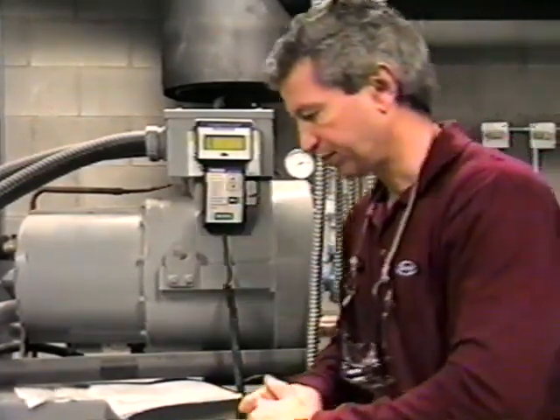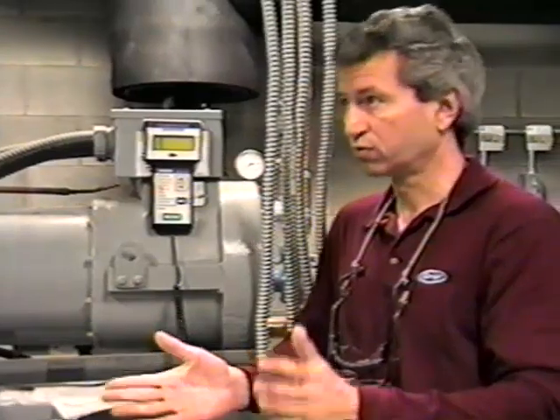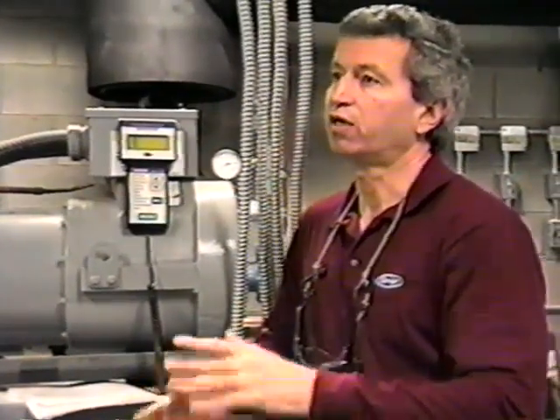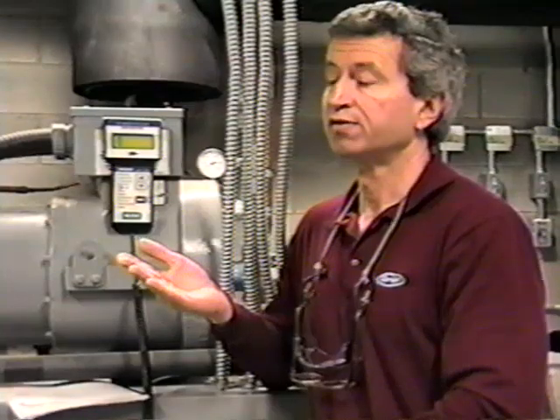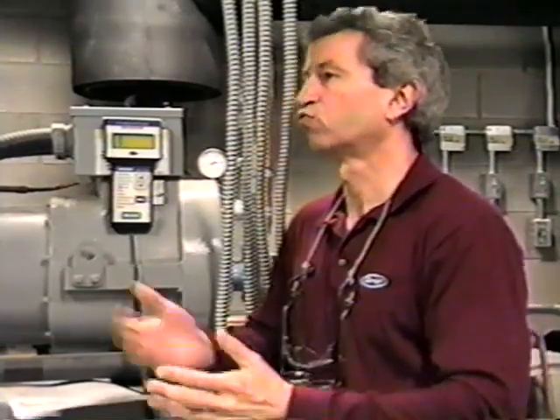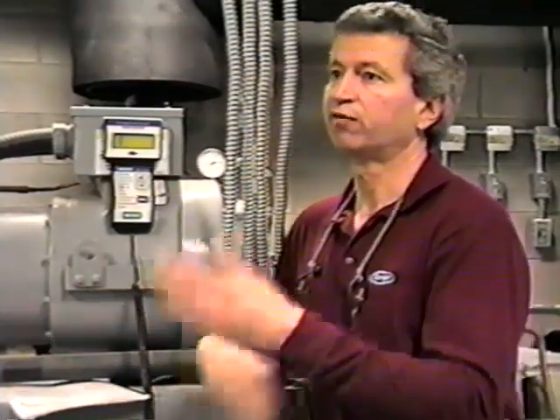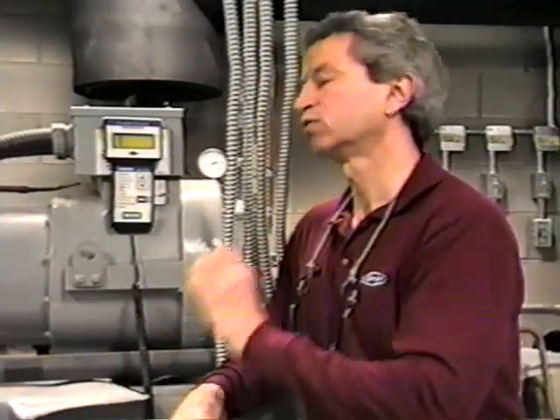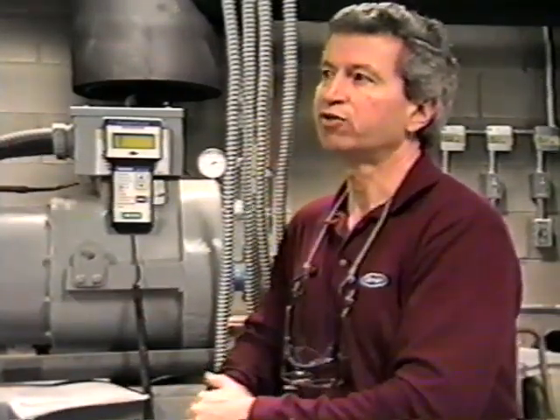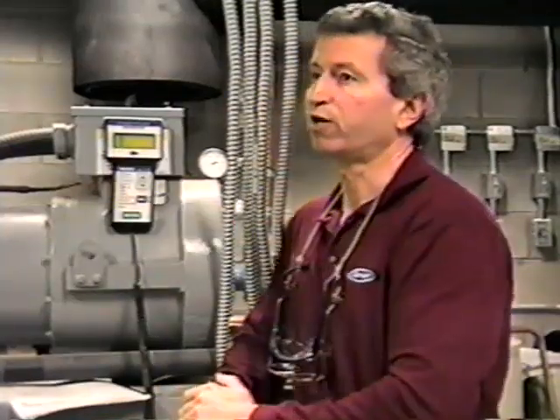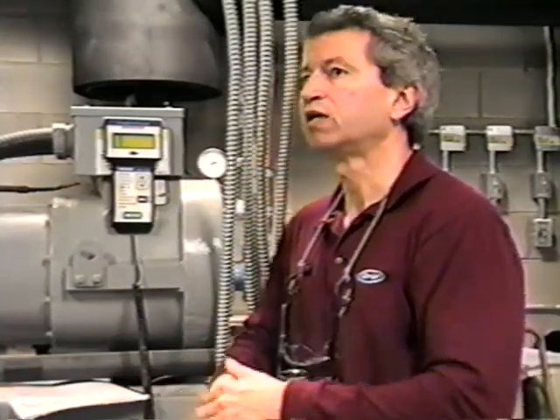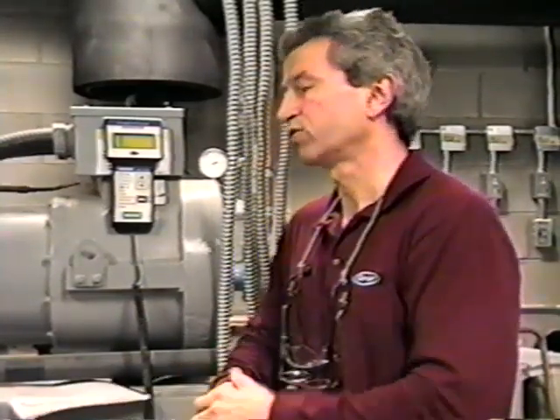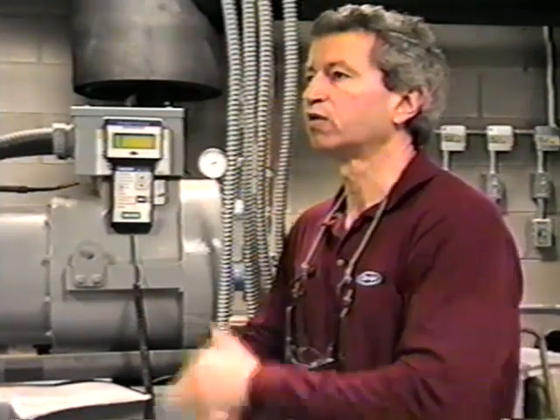Just a little note about head pressure. Head pressure is critical on a screw machine because it uses that head pressure versus suction pressure to drive the oil through the system, as opposed to just running an oil pump all the time. It uses that differential pressure to push the oil into the screws, into the bearings, and provide lubrication. So if for some reason that head pressure got unusually low, it might cause you to go into problems with maintaining oil pressure in the system and essentially cause you to go off on a safety. So it's critical that that head pressure is maintained at a nominal level.